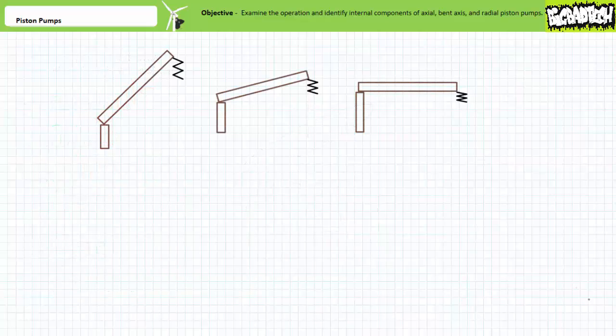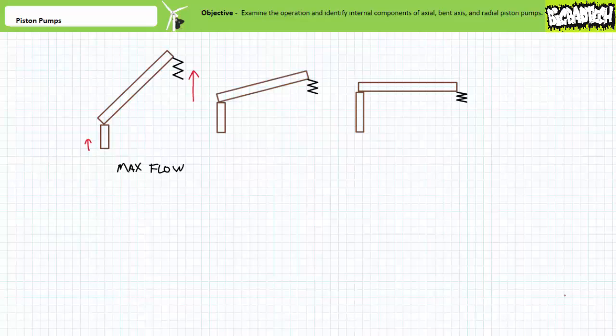Variable displacement piston pumps often use a spring and piston combination to adjust the angle of the swash plate, similar to the method employed by variable displacement vane pumps. When the piston exerts less force than the spring, the swash plate is held at a maximum angle and volume differential is at a maximum. When the piston exerts increasing force, the swash plate is held at less of an angle and the volume differential between the top of the upstroke and the bottom of the downstroke decreases.